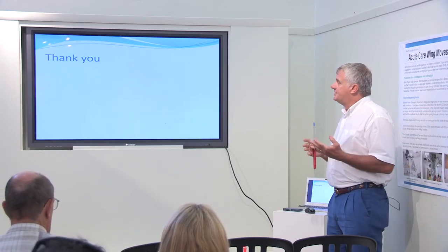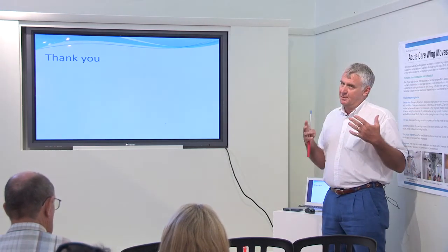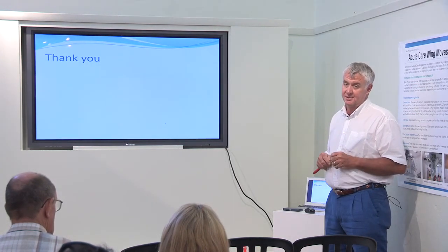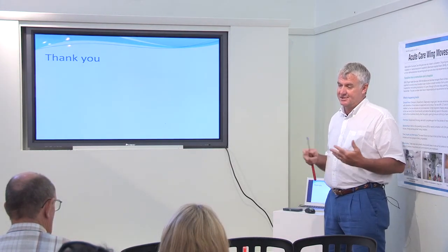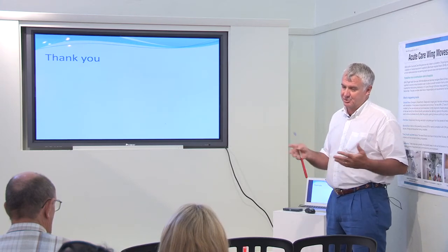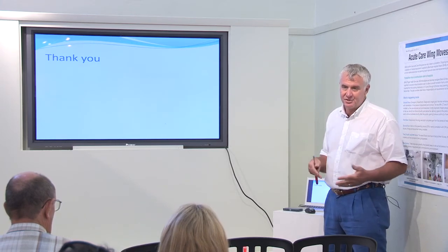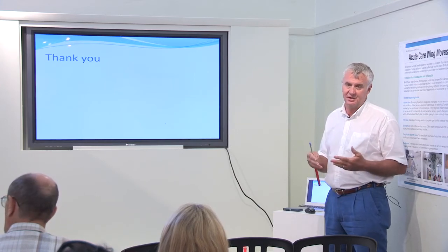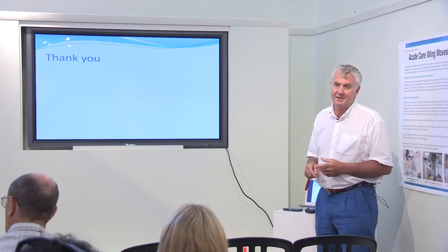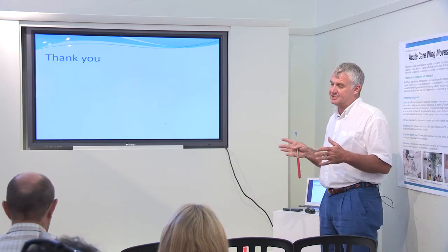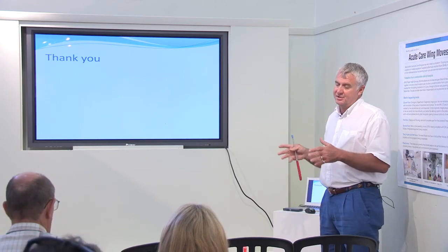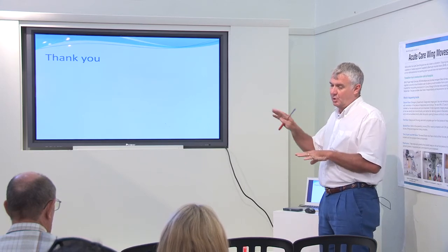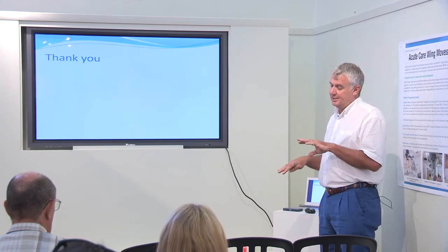It takes the maintenance that you would expect with mechanical and electrical equipment. So it needs to be maintained on a regular basis. Electric motors are checked, bearings are changed, all the sorts of things that you would do with a large air conditioning unit or a motor car. But it's designed so that there are two main streams. Anything that has a lot of mechanics or electrics in it has two streams, so one can be switched off and the other one run.